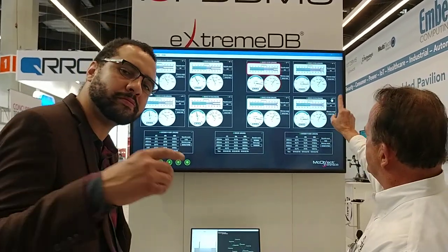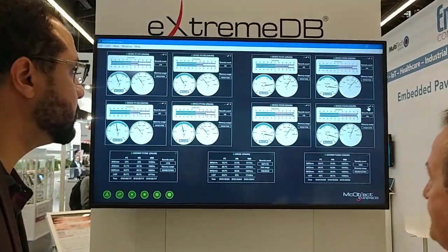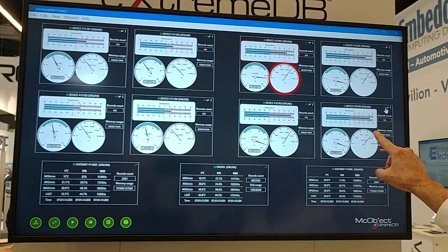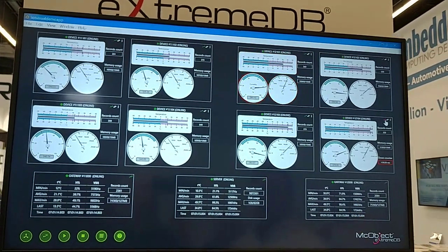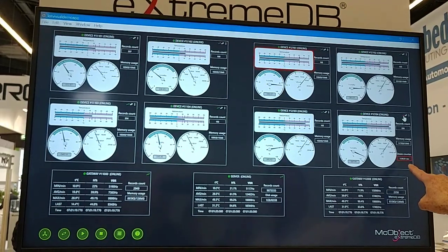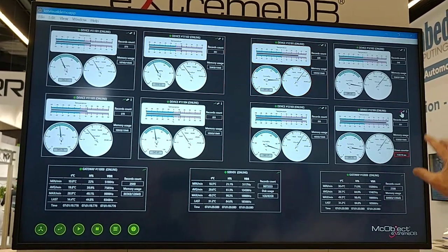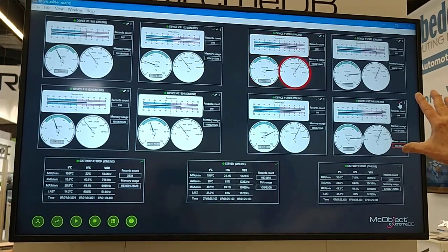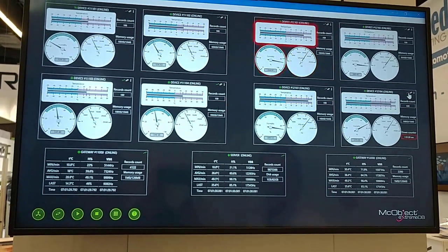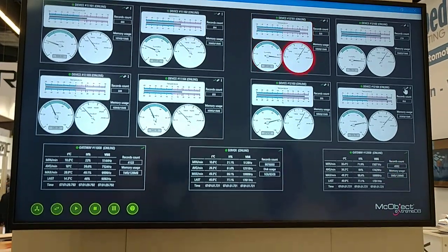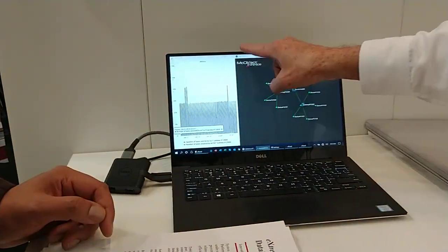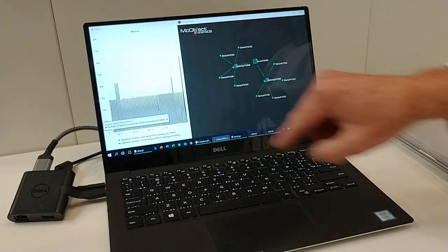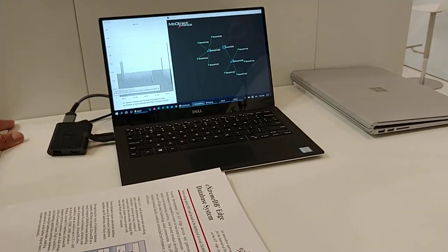Now what we can show is you can take it offline at any point, and this device is still working, still doing its job on the equipment, but it's lost communication with the gateway. And as you can see, it's telling us we have an hour and over 30 minutes left of internal memory to still accumulate data to refer to later. Whenever it comes back online, it sends data over the network, and you can see it spike up as it communicates to the gateway, and there you go. So we're automatically handling that for you.